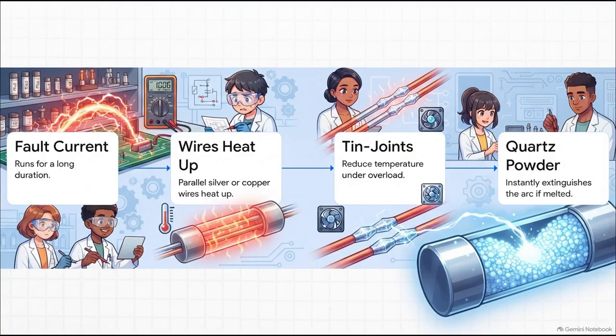HRC fuses are just phenomenally engineered. They have to be because they're designed to clear both low and high fault currents at crazy high speeds, all without needing any regular maintenance. Here is the step-by-step of how they work. First, the fuse element is taking on a fault current for a prolonged duration.